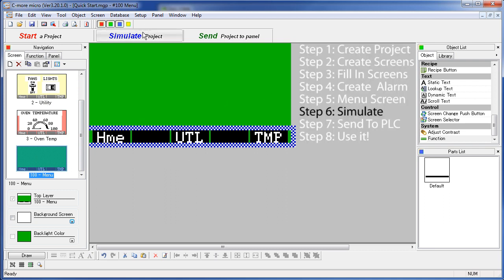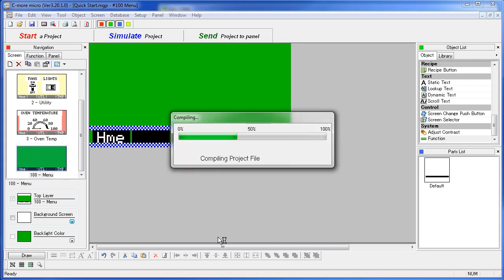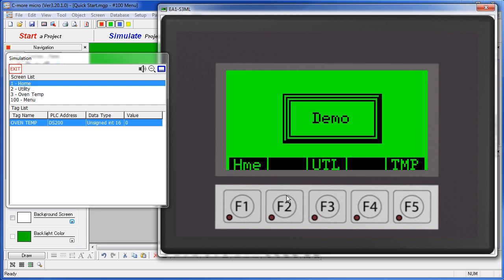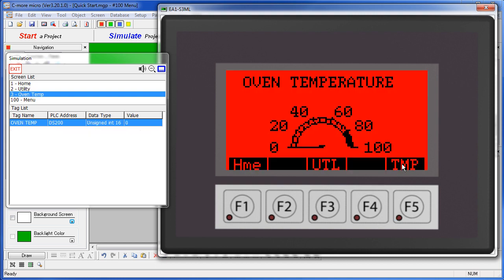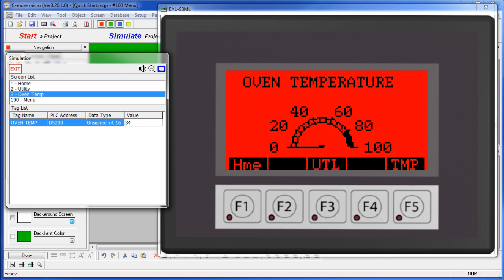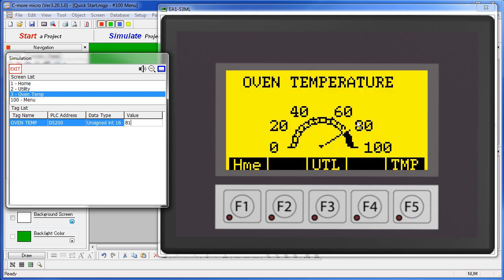Step 6 – simulate it. Hit the simulate button and up pops our simulator with the new project. F1 takes us home, F3 takes us to the utility screen where we can turn the fans on and off. The control window tells me what the tags on the PLC will be doing in the real project – when I flip the fan switch, the tag changes; when I flip the lights switch, the lights tag changes. On the temperature screen, the analog meter is monitoring the oven temperature tag. I simulate a temperature of 34 and the meter shows that. Setting it to 81 – over the 80-degree threshold – and sure enough we get the beeps and the blinking background alarm.